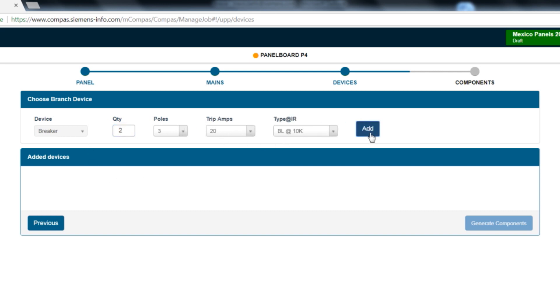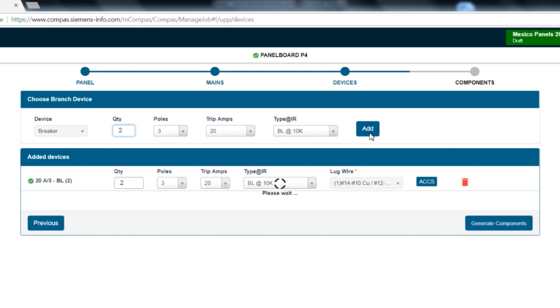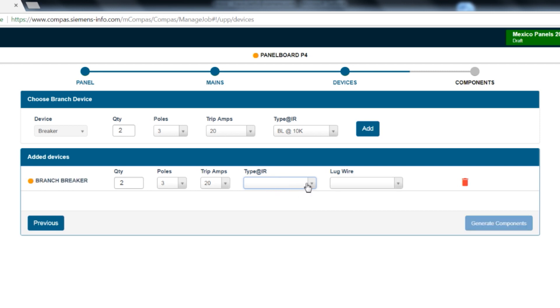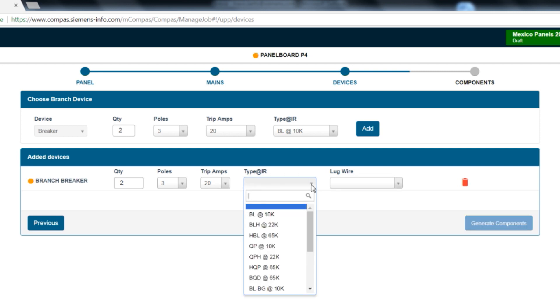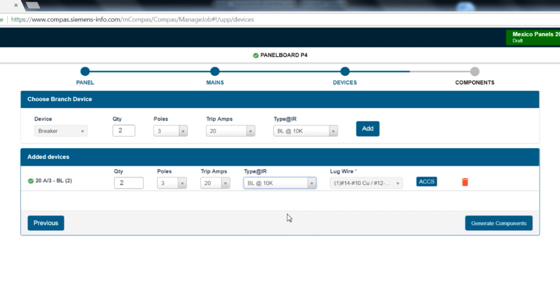In this example, let's select two 3-pole 20 trip amp BL breakers, then click add. If you need to add accessories or change the breaker type, do this after the configuration is added. Once added, you can reset the breaker selection and see all of the breaker options available. For this example, we will keep the breaker selection as BL.